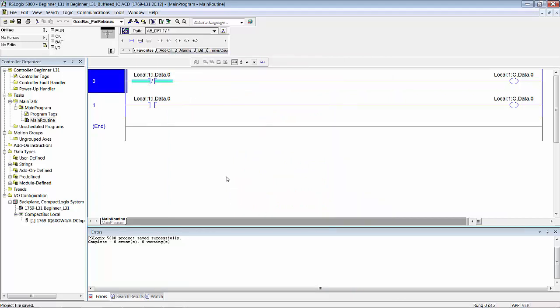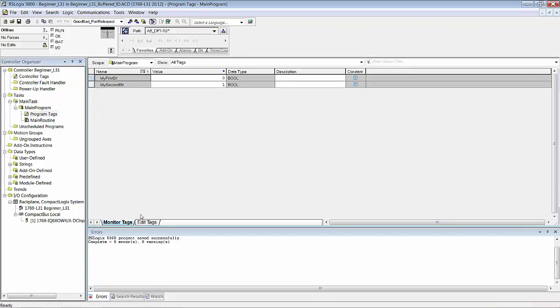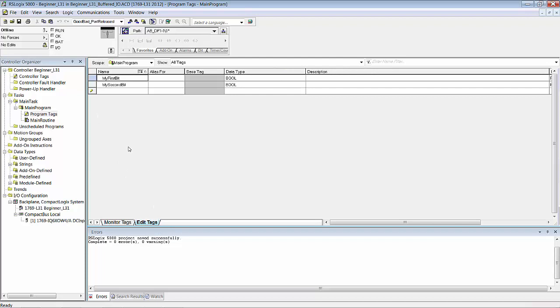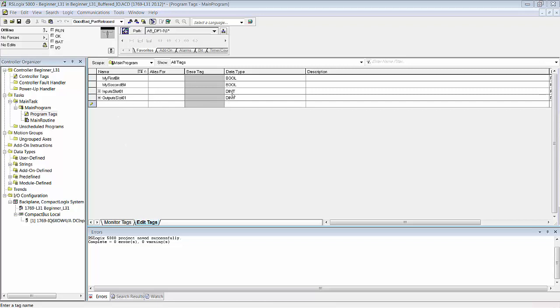I had you open up the main program tag database. Go to edit tags tab so you can add a new tag and create two new tags. Create these two new tags as dints, double integers, 32-bit words. You might be thinking there's only six inputs and four outputs so why not have single integers, 8 bits. But remember that the memory array in the chipset in the processor is 32-bit. You're not really saving any memory by using a single integer instead of a double integer.